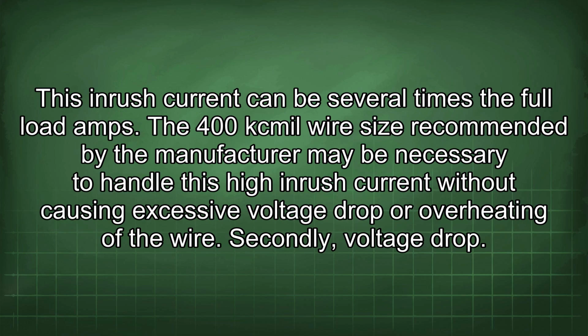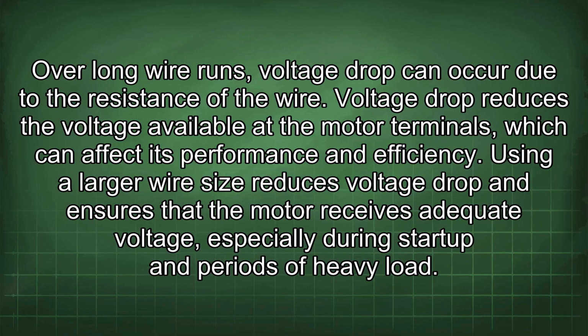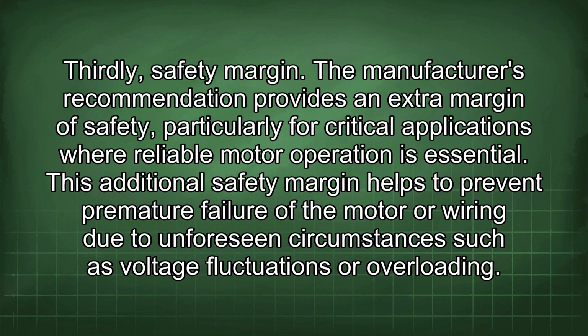Secondly, voltage drop. Over long wire runs, voltage drop can occur due to the resistance of the wire. Voltage drop reduces the voltage available at the motor terminals, which can affect its performance and efficiency. Using a larger wire size reduces voltage drop and ensures that the motor receives adequate voltage, especially during startup and periods of heavy load. Thirdly, safety margin. The manufacturer's recommendation provides an extra margin of safety, particularly for critical applications where reliable motor operation is essential.